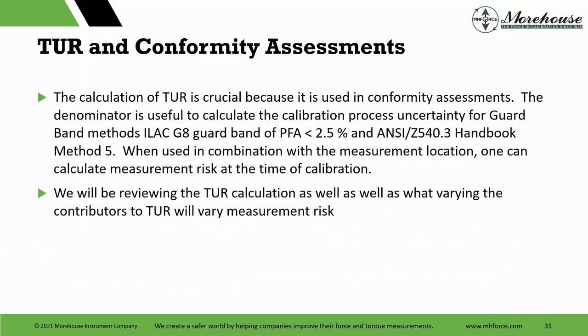So the calculation of TUR, people get this confused because there are documents out there that say if you have a 4-to-1 TUR, you don't need to worry. Be careful with those documents because a lot of them don't tell you the fine print, right? And the fine print is that it assumes that there's no bias in the measurement. That assumes the measurement is perfectly centered on the graph. You don't see that often.